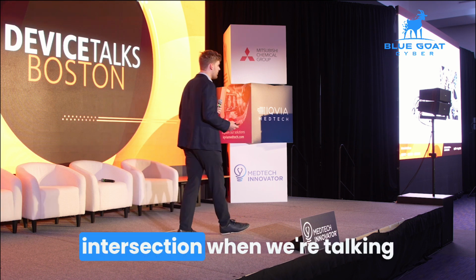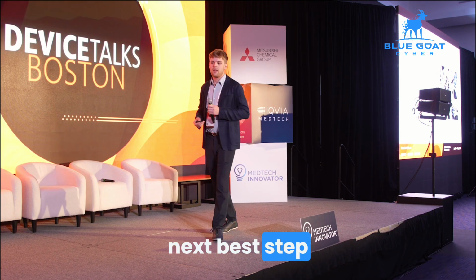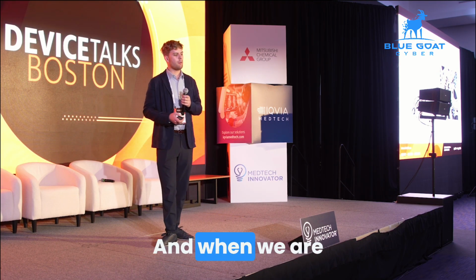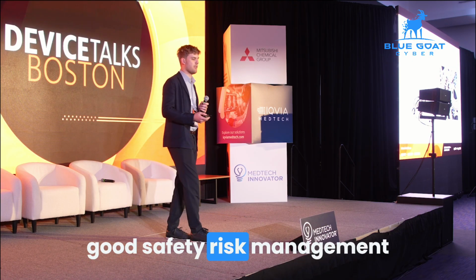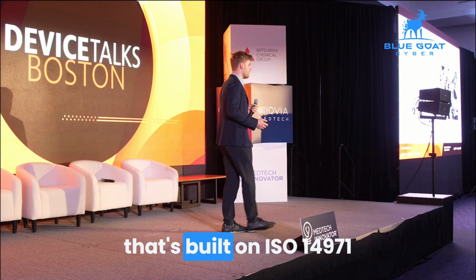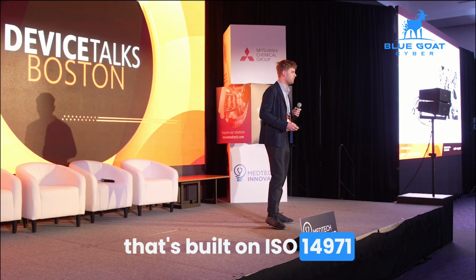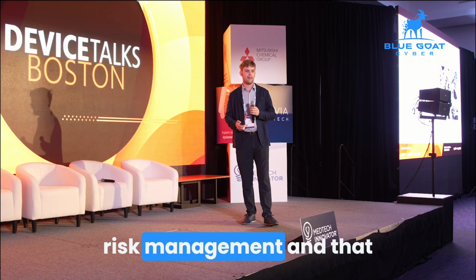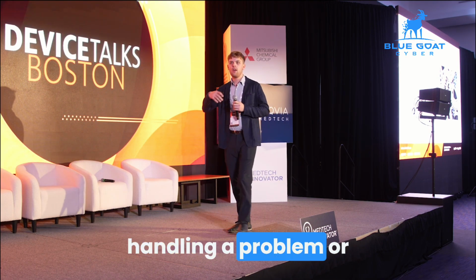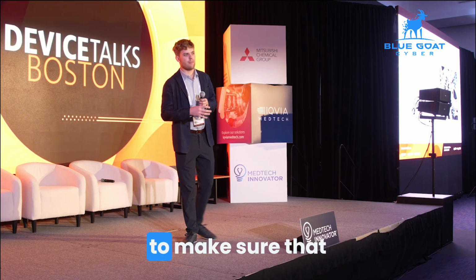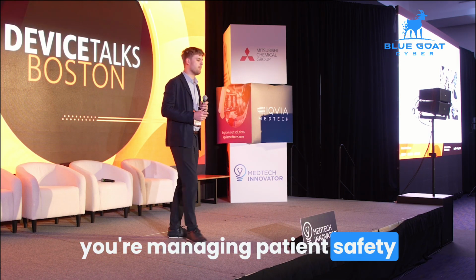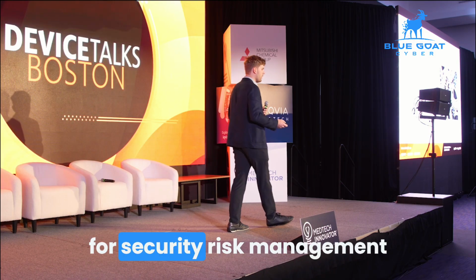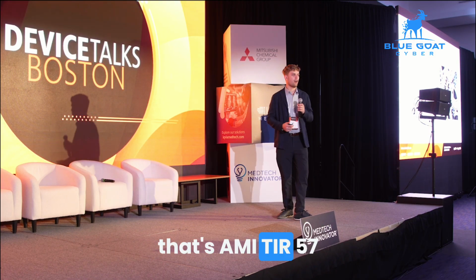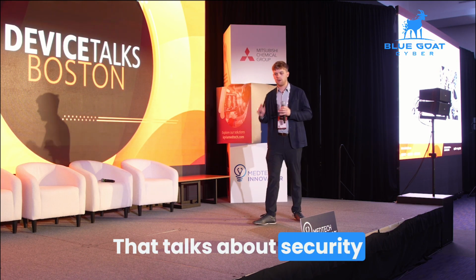There's a very close intersection when we're talking about a medical device. Obviously, security and cybersecurity, but safety is the next best step. They tie in very closely together, and when we're looking at what a good safety risk management framework is, that's built on ISO 14971. That is for safety risk management, and that talks about how you're handling a problem or any situation, how you triage it to make sure that you're managing patient safety. Now, for security risk management, that's AAMI TIR57. That talks about security risk management.